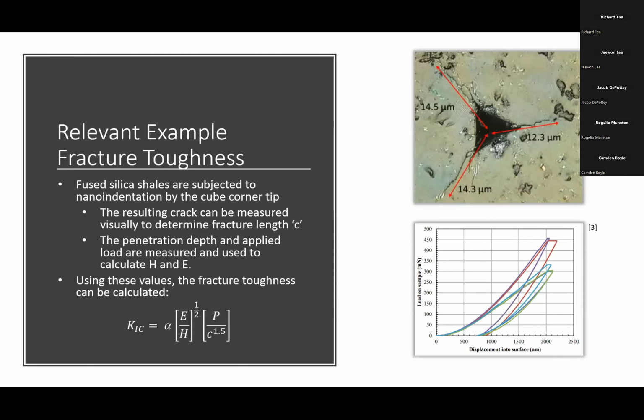So getting into some relevant examples that we have, the first one is measuring the fracture toughness of a brittle material. In this case, it's a fused silica slab subjected to nano indentation by a cube corner tip. You can see the picture there in the top right. It was indented with the cube corner tip, and there was a radial fracture from each corner. Using optical imagery, you can measure the distance of each of those fracture patterns, and you could label these C. The penetration depth and applied load are measured as we usually do and used to calculate the hardness and Young's modulus. And then using all of these values that you've collected, you could calculate the fracture toughness using the equation I have there on the bottom.